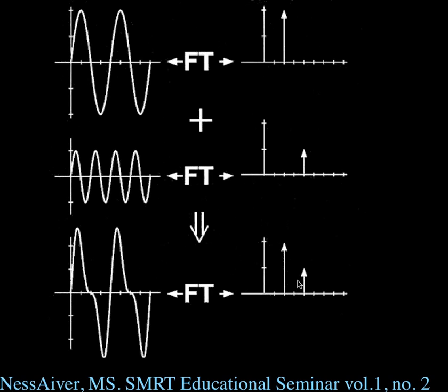So we receive all the signals all the way through. Okay, and then the center of that will depend upon the center frequency of the magnetic field. If it's 1.5 Tesla, the center of that bandwidth will be somewhere around 64 megahertz. Okay?